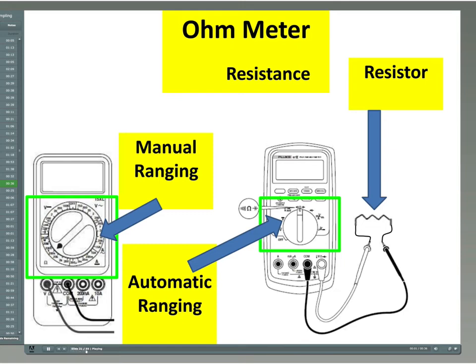Meter types are available: the automatic ranging meter and the manual ranging meter. The auto ranging meter has fewer choices to move the selector switch to, and the selector switch does not need to be adjusted when reading varying amounts of voltage, current, or resistance. The meter makes those choices for the operator. The operator must keep an eye on the changing engineering units after the value, like K and M, when in the ohm meter mode. The manual ranging meter makes you work the range switch up and down the engineering unit's scale.